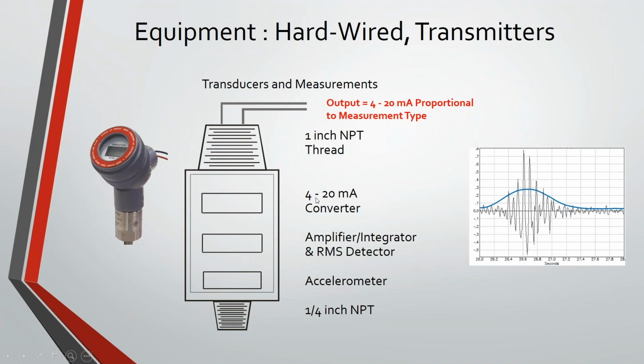And then we're going to have an A/D converter turn this into a 4-20 signal for us. Now what we have is this two-wire loop-powered output, and that's going to behave a lot like pressure transmitters that you might be familiar with elsewhere in the facility. That's a convenient signal. We don't need a signal conditioner, and we don't need specialized equipment to trend it. So that's a really convenient way to do sensors.